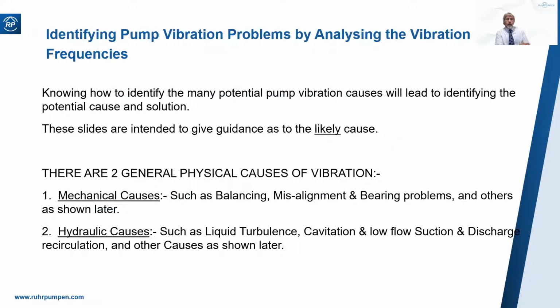So, why is your pump vibrating and is it serious? This is what we're going to look at today. There are 2 general physical causes of vibration: mechanical causes, balancing, misalignment, bearings, and hydraulic causes, liquid turbulence, cavitation, and suction and discharge recirculation.